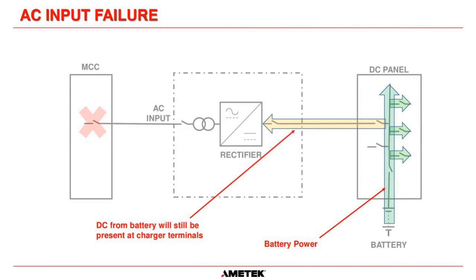Now, if you had a failure, either grid power has been lost or something has happened at the MCC and we have lost AC power to the system, the battery now takes over, and the battery will supply load to your DC circuits. There's no switching involved. It's just like pulling the AC input plug out of your laptop. There's no switching. The laptop carries on going regardless because the battery is in parallel with the DC bus.